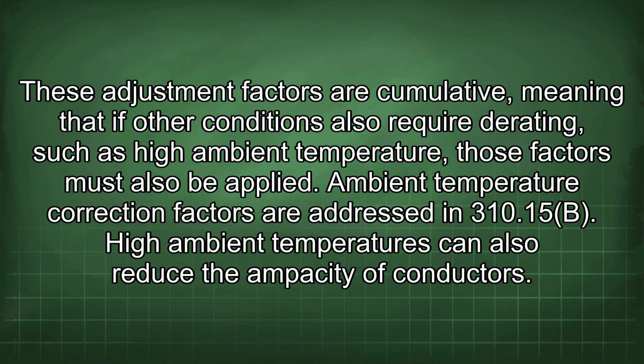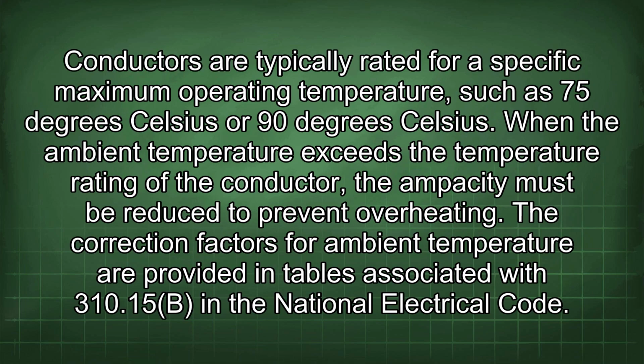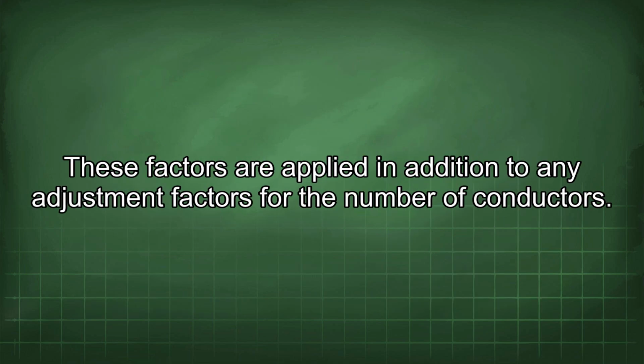High ambient temperatures can also reduce the ampacity of conductors. Conductors are typically rated for a specific maximum operating temperature, such as 75 degrees Celsius or 90 degrees Celsius. When the ambient temperature exceeds the temperature rating of the conductor, the ampacity must be reduced to prevent overheating. The correction factors for ambient temperature are provided in tables associated with 310.15(B) in the National Electrical Code. These factors are applied in addition to any adjustment factors for the number of conductors.